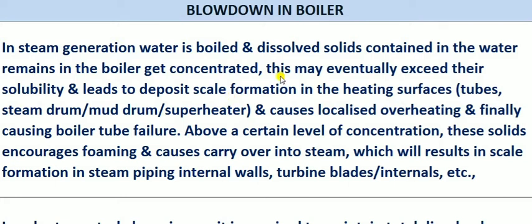When mud and scales get formed on the surface, the heat transfer will get reduced due to the resistance of the scales. So localized heating will occur, which causes tube failure. To avoid that, there is a standard for how much concentration of solids we want to maintain in the boiler. The ASME standard applies, and the boiler vendor also provides certain parameters for how much concentration can be maintained.